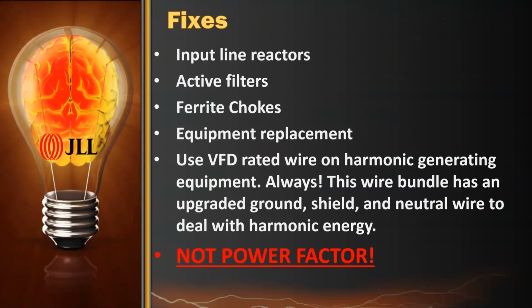So chokes are going to be cheap. They won't do quite as good a job as an input line reactor. So let's define quite as good. If I've got a 20% harmonic, a choke is probably going to get me down to 5%. With an input line reactor, I can get down to 2%. On a 1,000-ton chiller, I'm going to spend on ferrite chokes, I don't know, $500-600 of material. On an input line reactor, I'm probably going to spend about 15,000, but I'll get the extra 3%.